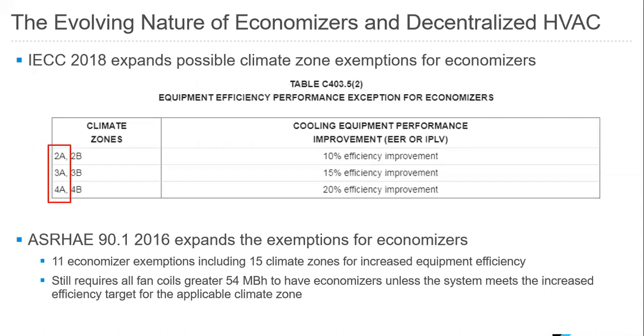So the evolving nature of economizers and decentralized HVAC, as Jason pointed out, IECC 2018 expands the possible climate zone exemptions. So it does include 2A and 2B. You still have to meet the efficiency improvement requirements per zone. So for 2A, 2B, it's 10%, 3A, 3B, 15%, 4A, 4B, 20%. And ASHRAE 90.1 2016 actually expands the exemptions for economizers.